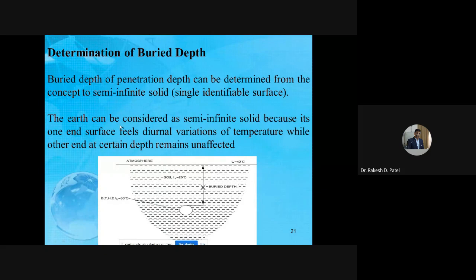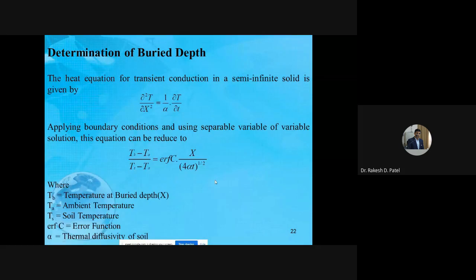So the Earth can be considered as a semi-infinite solid because one end surface feels the diurnal variation of temperature, while the other end, at a certain depth, remains unaffected. So the buried depth is determined from this simple thermal equation for a semi-infinite solid, applying the boundary conditions and using the separable variable solution. This equation can be reduced to find x. The x is the buried depth for the heat exchanger.